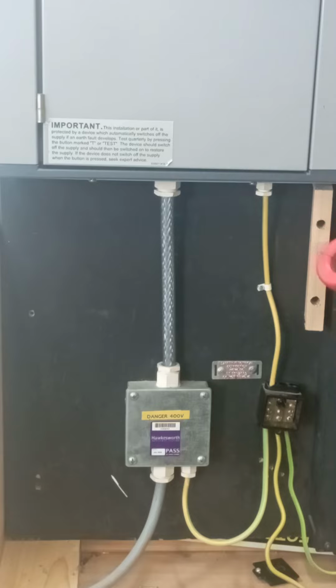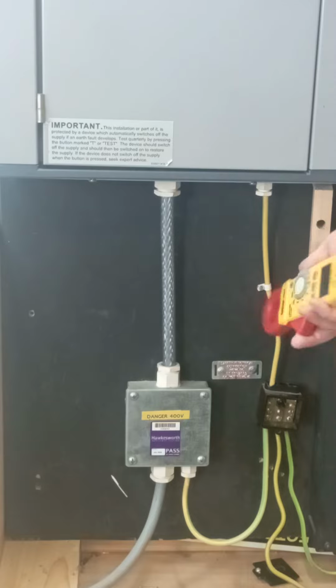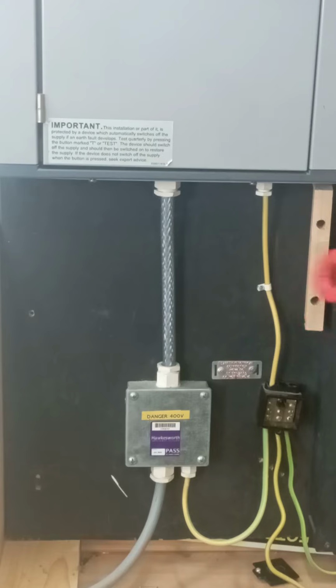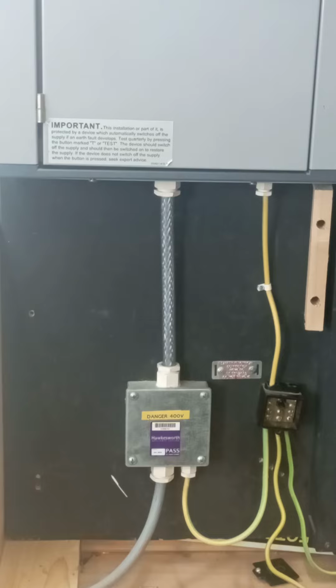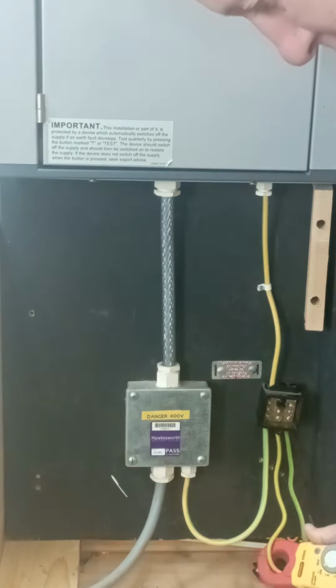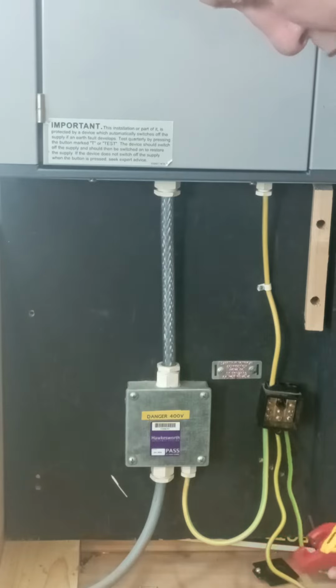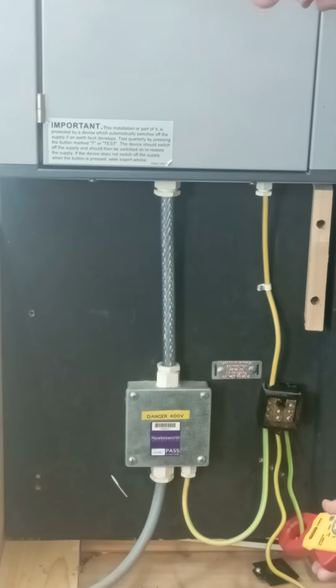Now, once we've checked that, bearing in mind in a real installation we might have parallel paths within the installation, that might not actually be a true value that we've got on the CPC, because again, as I said, it might be circulating in all of our earthing and bonding arrangements. So this installation here, you'll see we've got two main protective bonding conductors. It's going down to 0 milliamps on the main protective bonding conductors when I'm clamping them.